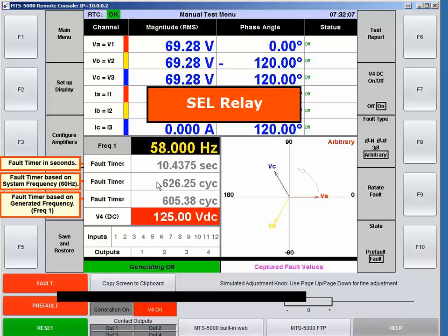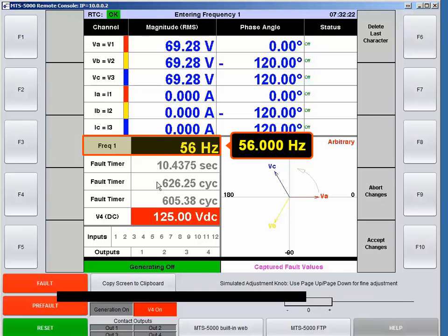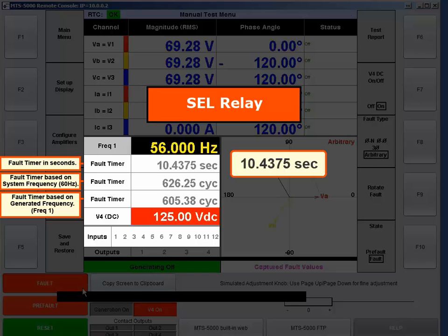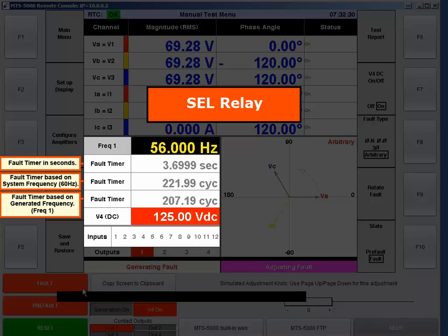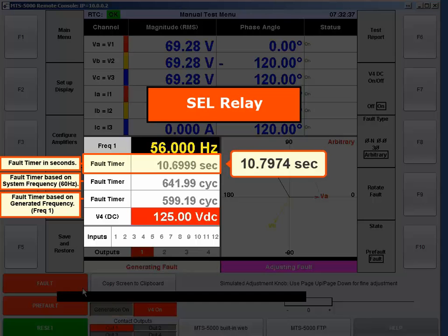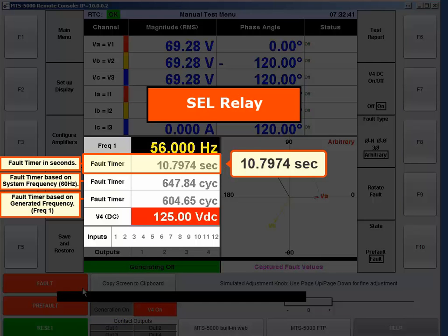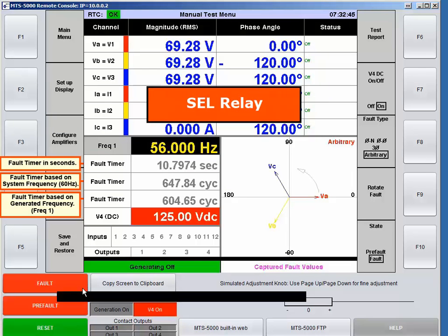If you're ever in doubt, the easiest thing to do is change the frequency. If you get a different number in seconds, you know the relay is calculating cycles based on what you're generating. At 56 Hz the test came in at 10.79 seconds, compared to 10.4375 seconds at 58 Hz — a difference of about 0.3 seconds, which is almost forever in electrical terms. If you do the same test on a Beckwith, it continues to output 10 seconds regardless of the injected frequency.